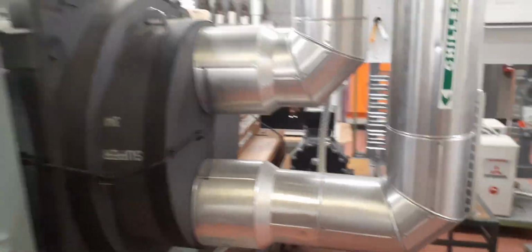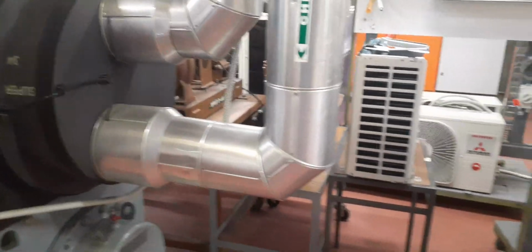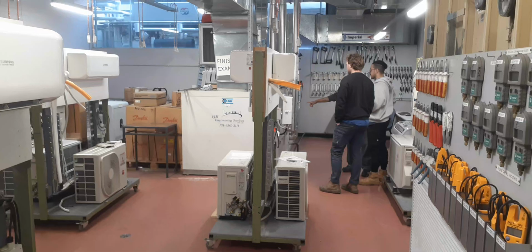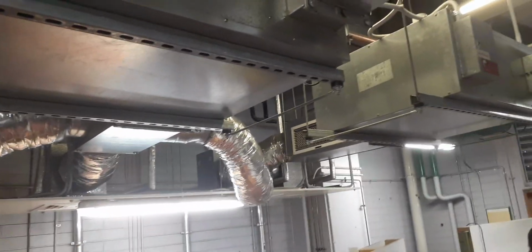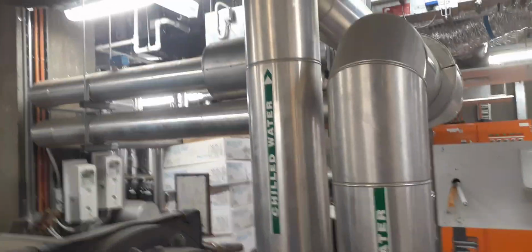So your chilled water lines. What happens is your water comes in from the field, right? It's going in the bottom. And what do we mean by the field? Well, we've got things like the air handling unit over there. We can see the supply duct coming off here, and it's going to the VAVs. These ones up here, Wes, are VAVs, yeah? Okay, so that's your field. This is only a small little plant.